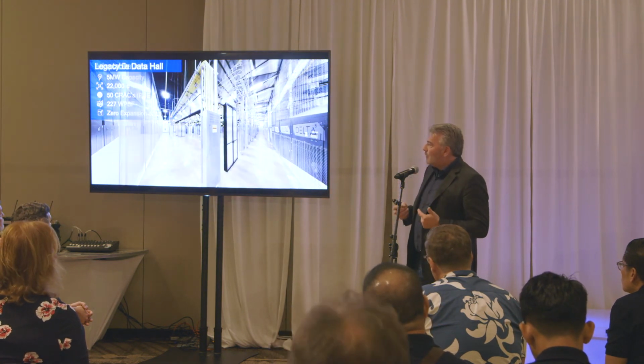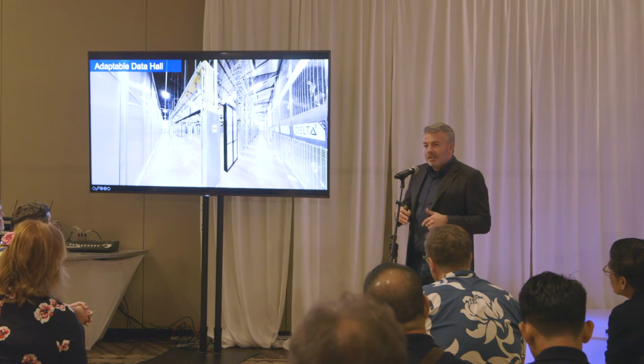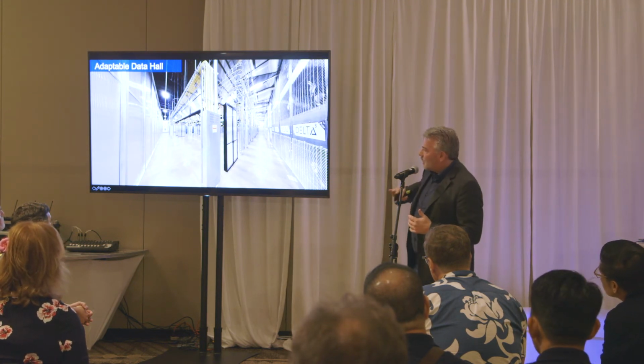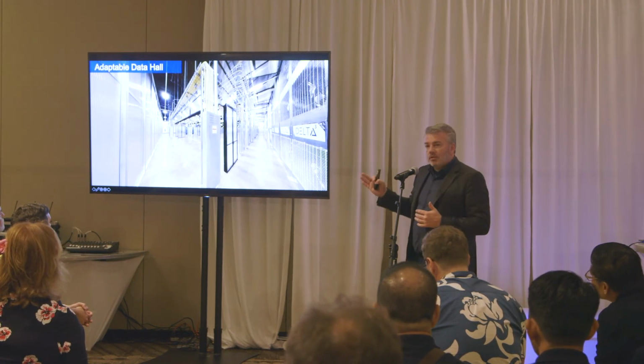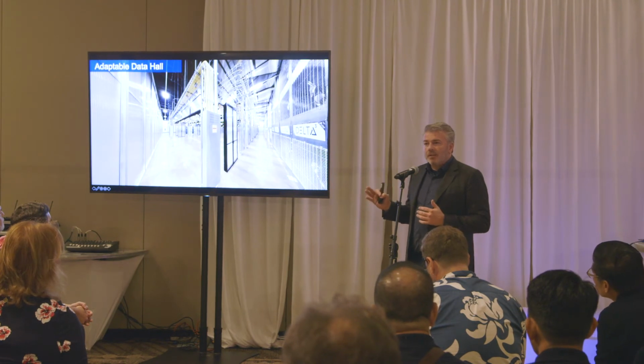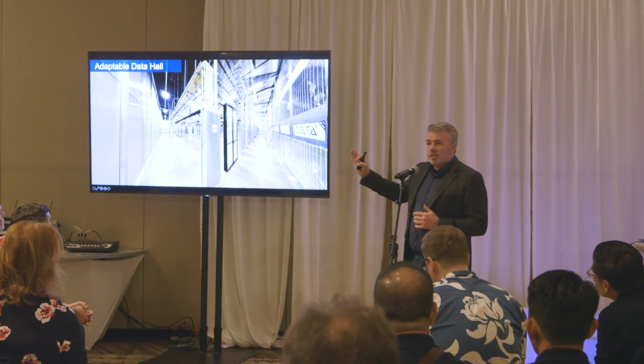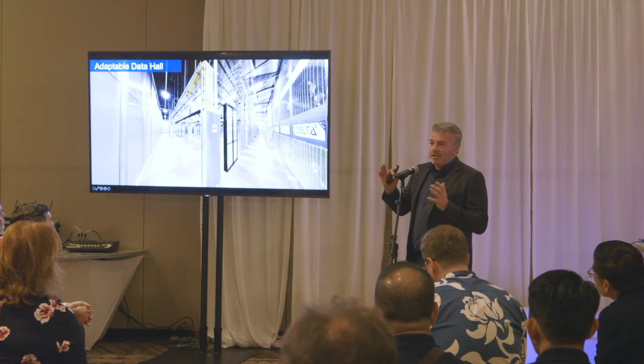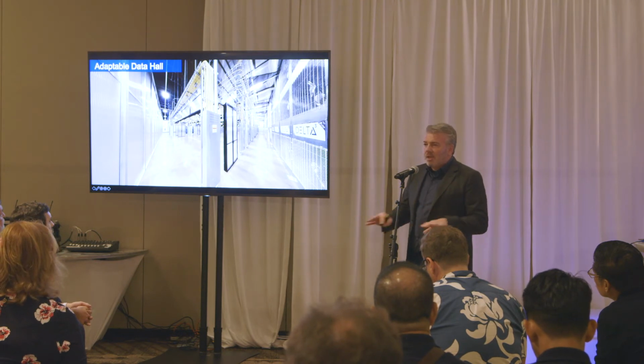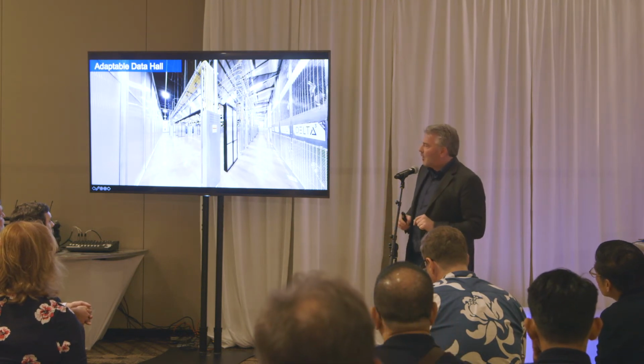So it's time for an adaptable data center. Here you can see no raised floor, which a lot of new customers are very happy about. They do their rack and stack and burn-in off-site, then just roll in these incredibly heavy, fully laden cabinets and plug them in. You can't really do that with a raised floor - you'd have to put down melamine, crack the floor tiles, it's horribly expensive.